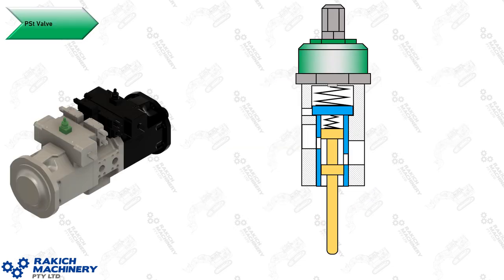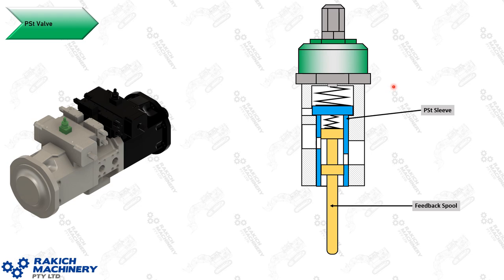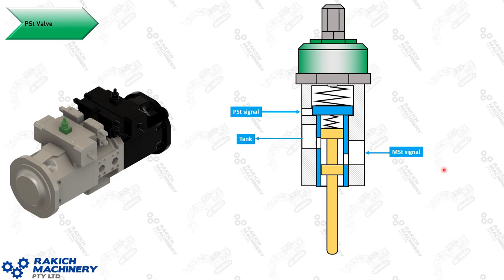I'll be using a schematic of the pump to explain the function of the system through the presentation. However, the PST valve is really difficult to represent as a schematic symbol that's visually intuitive on how it works, so I'll explain using this basic cross-section diagram. Inside the valve you've got two concentric spools: there's a PST sleeve and then inside of that is the feedback spool. Their main responsibility is to act as a variable orifice and control the MST signal that enters the valve by opening and closing this orifice.